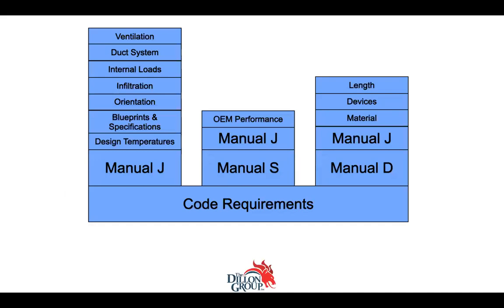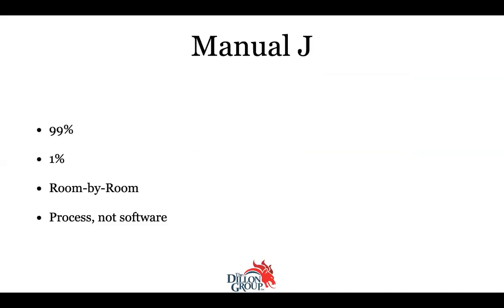So when I started looking at, what are the code requirements? These are the code requirements, Manual J, Manual S, Manual D. Manual J is all about doing the load calculation so that you can have a sense of the heating and cooling loads that then get plugged into Manual S, so you can select the correct piece of equipment to meet the demand. And it gets plugged into Manual D so that you can get the HVAC duct system designed so that it can deliver the right amount of BTUs to take care of the load. And so, it starts off with these code requirements, and then here's all the stuff that goes into it. And then we look at Manual J.